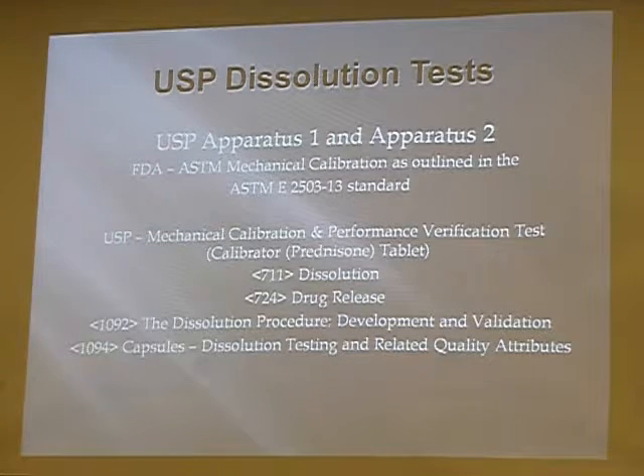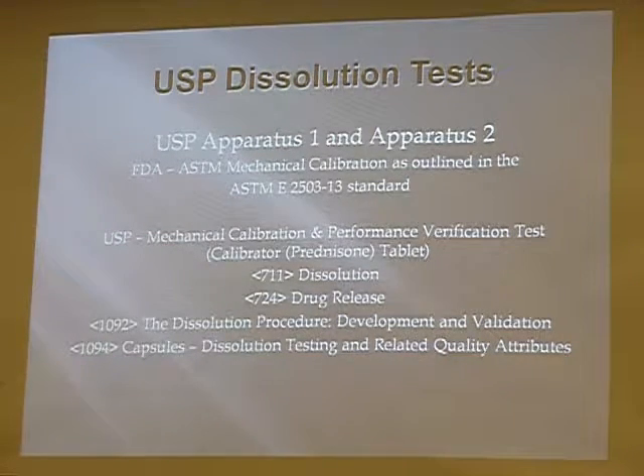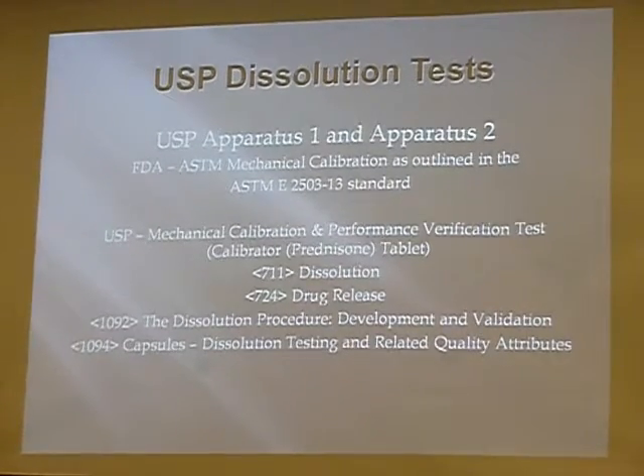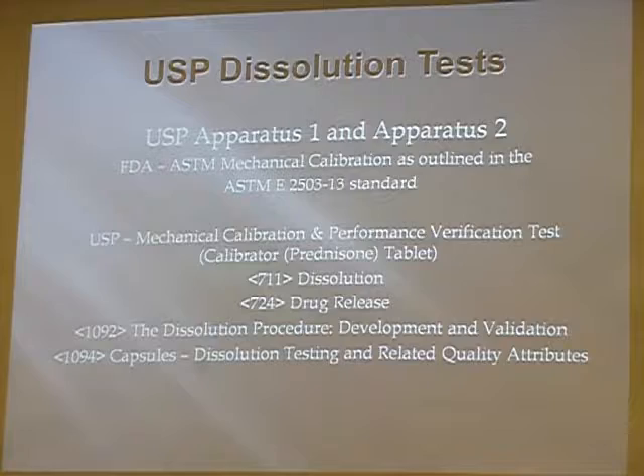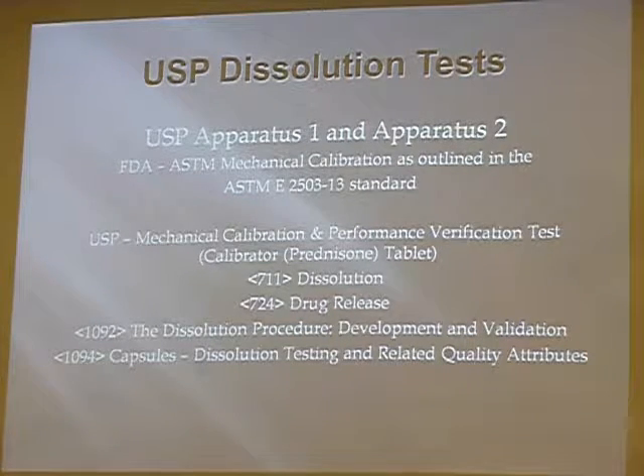Again, the different standards that are applicable: FDA, the ASTM E2503-13 standard. USP has the mechanical calibration and the performance verification test, which is the calibrator tablets. USP 711, 724, 1092, and 1094 all encapsulate what we're doing with the mechanical and the chemical testing of each one of the apparatuses. So if you have any time on your hands, or you want to be thoroughly bored even more than by my conversation up here, you might want to pull out USP and read some of those chapters. It's dry as you can see. I don't know if you've ever read it and looked through it, but it's there, and it's very well specified in each one of those. I'm going to put the document up on there, and we can go through it and start looking at some of these.